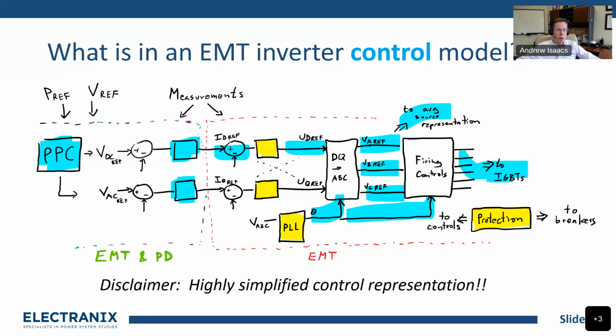And you also have on the other axis some kind of a current control. Again, if you're using a DQ reference frame, you'll have a current comparison at the terminals that's going to be controlling the Q-axis voltage, or the voltages, so that at the end of the day, when you're generating a voltage source with your IGBT bridge, you're going to produce the active and reactive power that you want.